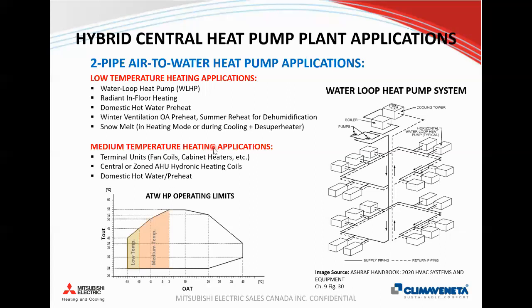So really, when it comes to applications, you just want to find the lowest temperature water possible, because that's going to maintain the higher efficiency from the heat pump. And really, the objective is just ensuring that you're going to be able to run that heat pump for the most amount of time as possible, because that will lead to more savings long term.